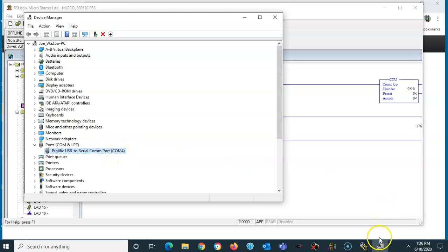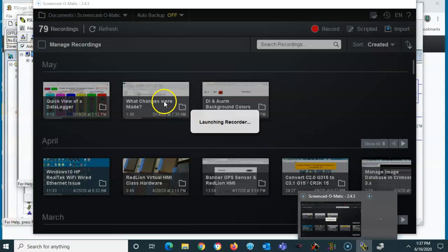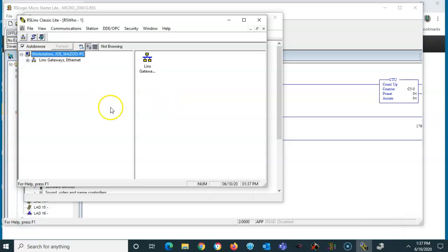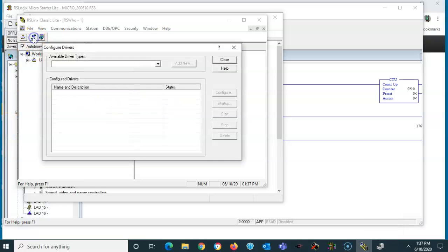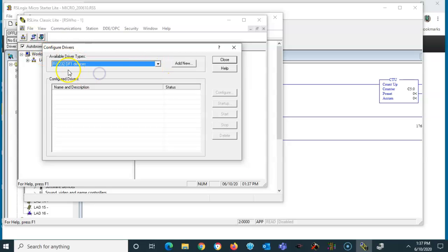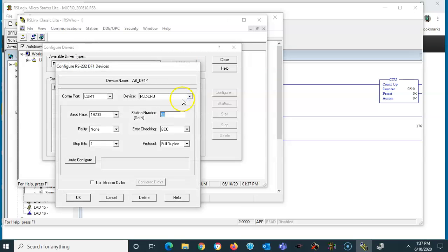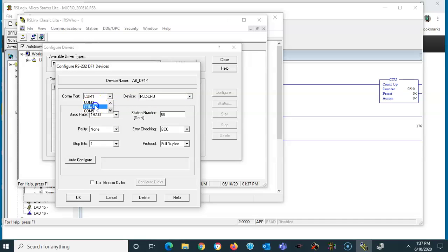All right, now that we know that, I'm going to go over to RSLinx, which is a Rockwell software. In RSLinx, I'm going to go ahead and configure a driver right here. I'll hit the pull-down here and I'll go down to, I'm going to pick RS-232 DF1, and I'll hit Add New. It comes up here, no big deal. I'll click OK and I'm going to choose the COM port number 4, because that's what the Device Manager told us. I'll leave everything else here by default.